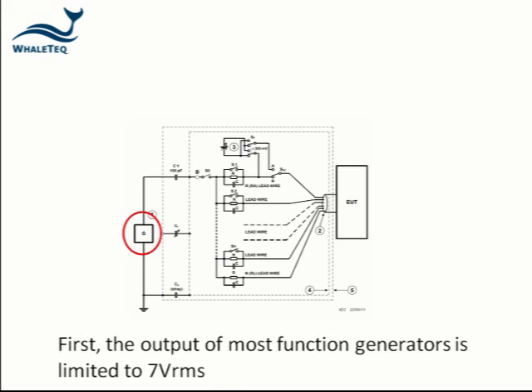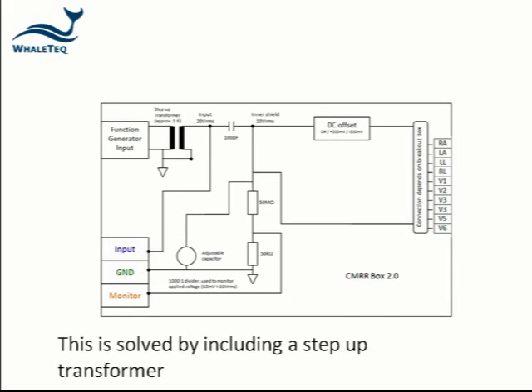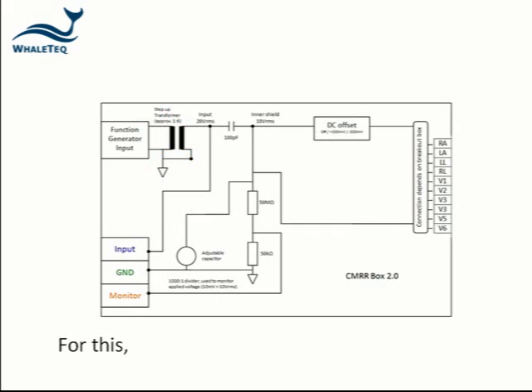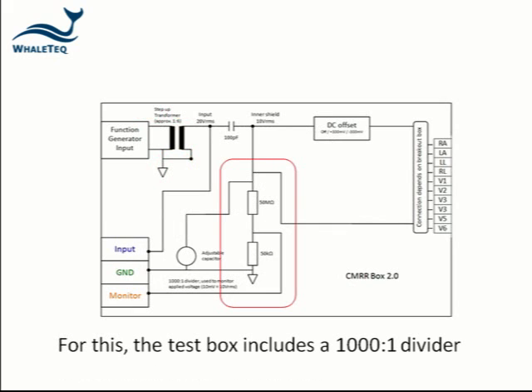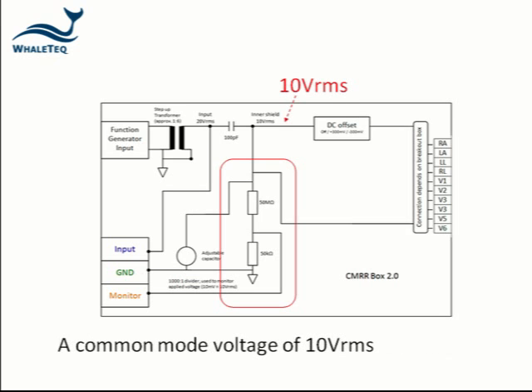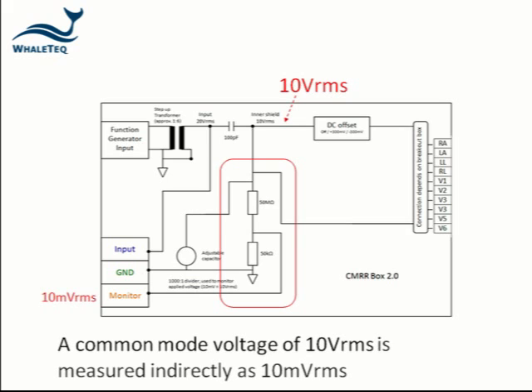First, the output of most function generators is limited to 7 volts RMS. The CMRR box includes a transformer to step up to 20 volts as required by the standard. Second, at mains frequency, 100 pF capacitors are very high impedance, which means that it's very difficult to directly measure the 10 volts. For this, the CMRR box includes a special 1000-to-1 divider, so that an output of 10 volts can be measured indirectly as 10 millivolts.